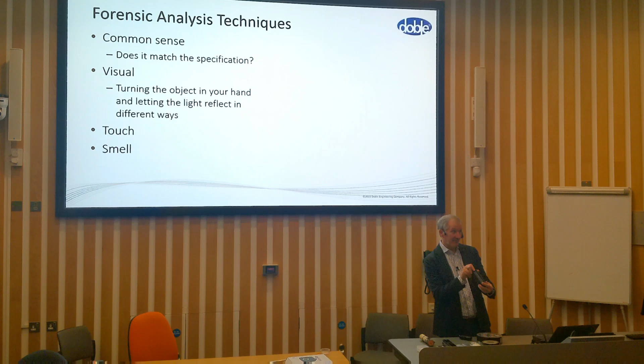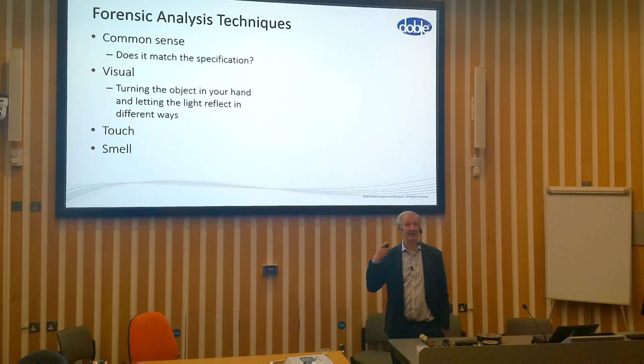Smell, maybe not quite so much. There was a case a few years ago where some of the evidence was, we opened the cable termination, I could smell burning. What he actually meant was I could smell partial discharge and arcing, you could smell acetylene. And that was in one that hadn't failed, but the fact that he said he smelt it told us that something was suspicious with that one as well, so we investigated.